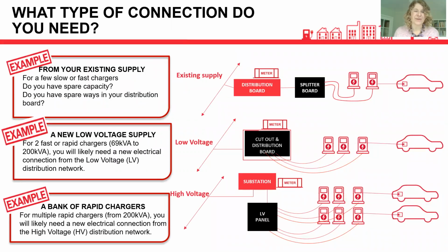So I'm going to start with a very quick overview of powering EV chargers. There's pretty much three ways to do it. First, if you're looking to install just a couple of slow chargers, say 3 kilowatt or 7 kilowatt chargers, you might have spare capacity on your existing supply. If you have spare ways in your distribution board, great. If not, it can be as simple as upgrading your distribution board.